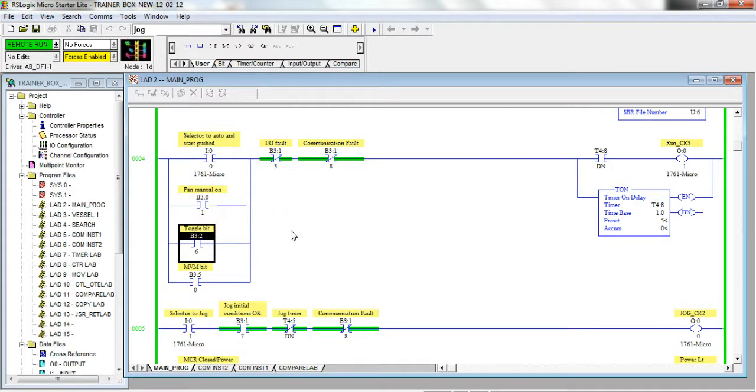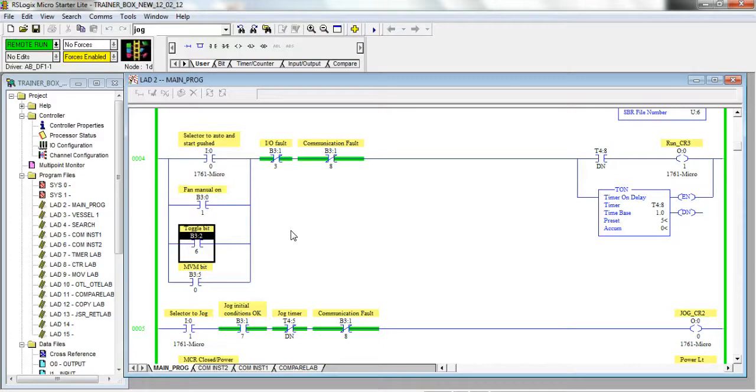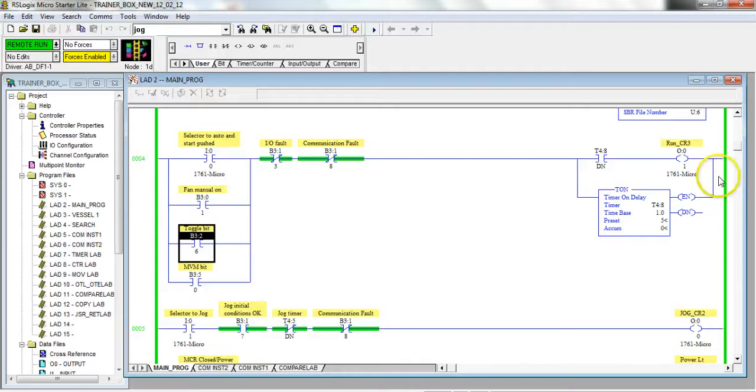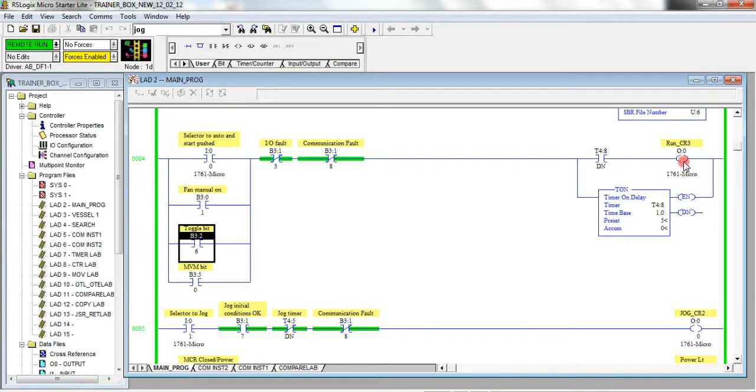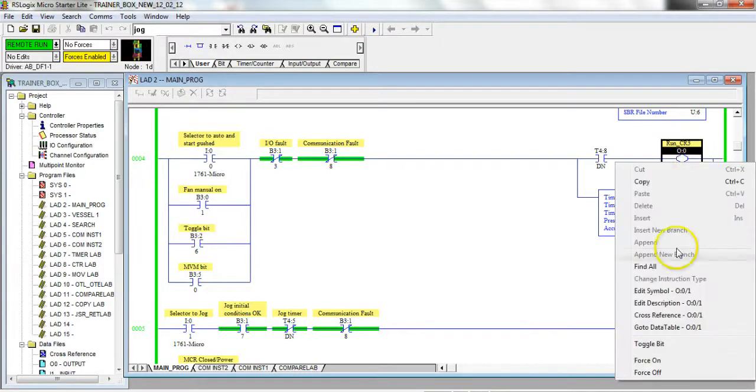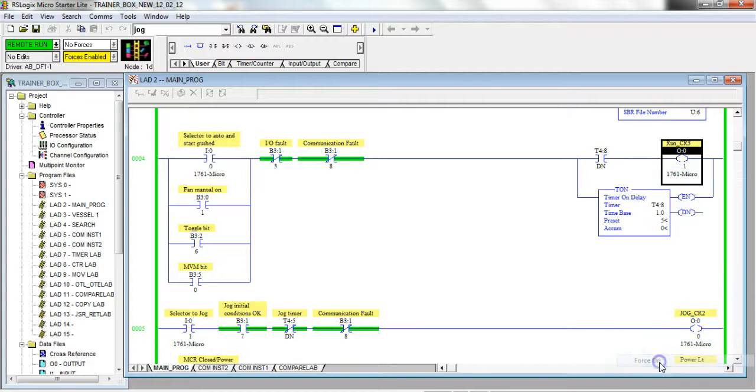So that's toggling - remember it's going to toggle everywhere in the program and you need to fully understand and fully search out everywhere that bit is used. Then there's forcing also. We'll look at forcing of outputs. Here's this run control relay three. If I force this on, my motor just started. You'll see it's forced on.